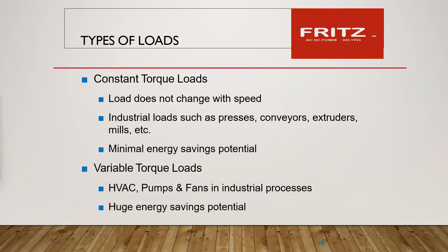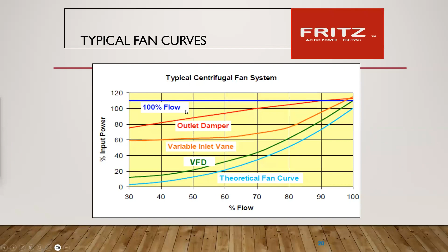Again, a little bit more information about constant torque loads, variable torque loads. Your dampers, controlled with a VFD here, shows the curve rating of horsepower and input power required, compared to outlet dampers, variable inlet vanes, or if it's just a straight 100% flow going out of the particular fan.